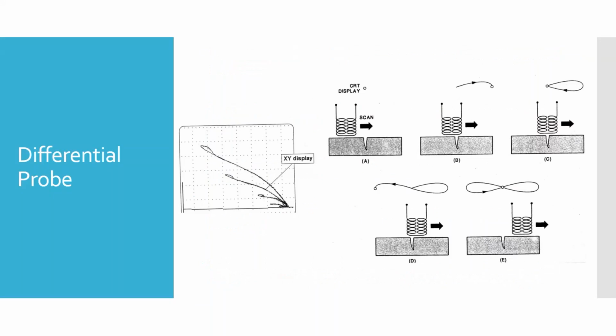This shows if we take that probe with two coils and run it across a flaw - this A, B, C, D, E - it's showing this probe being run across a crack and what kind of indication you might get. In a real, balanced, perfect scenario, you can see it creates this infinity symbol, and you can see the progression here. We start with our probe not over the flaw at A, and then as one of the coils starts to get over the flaw, that pulls the indication one direction - in this case, off to the right.